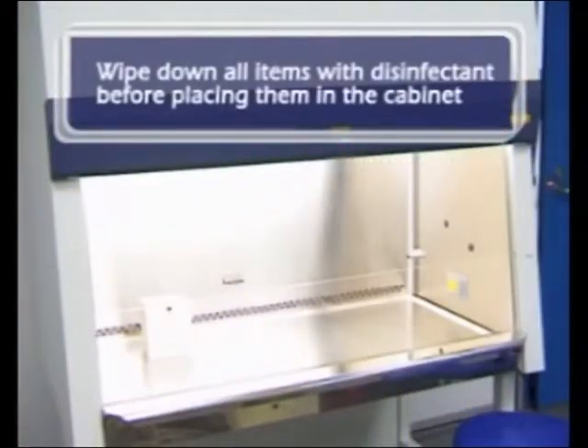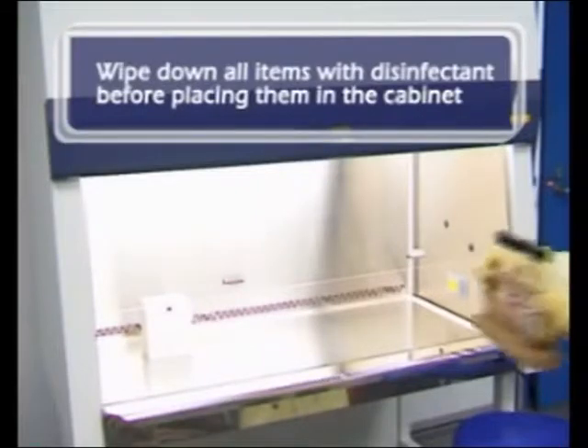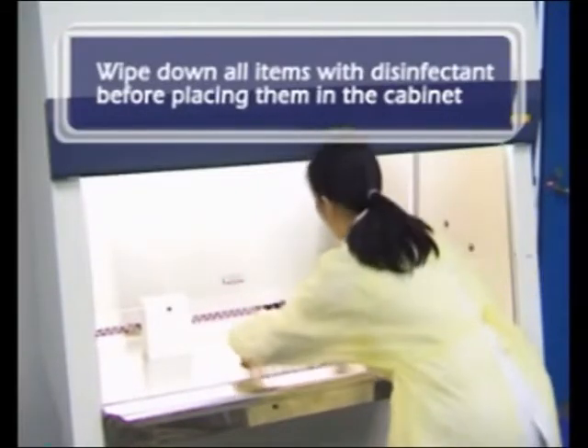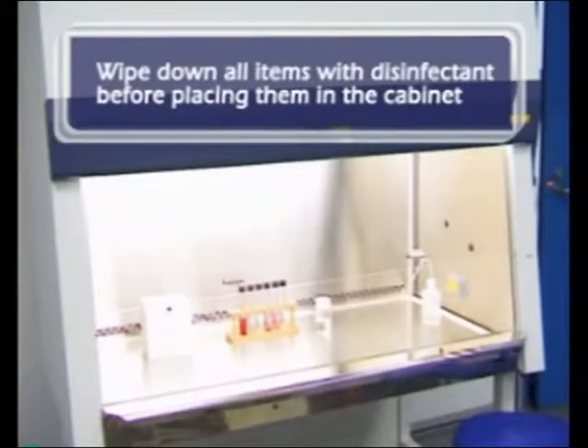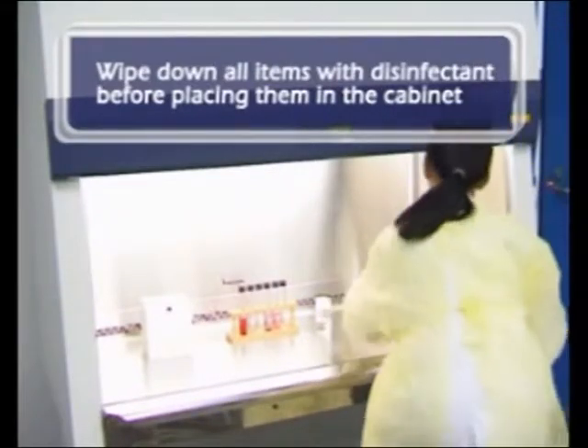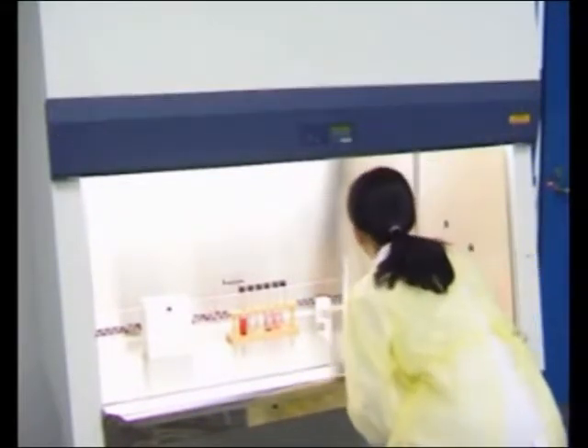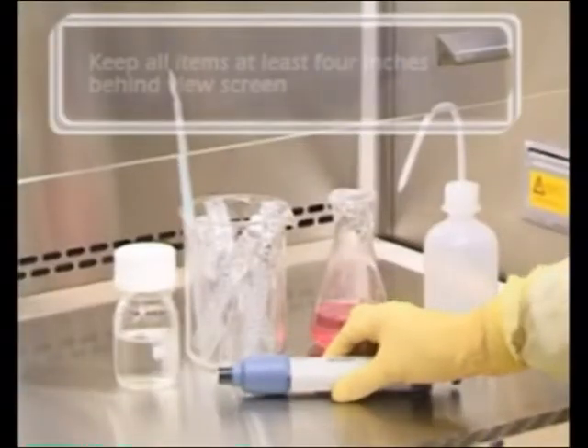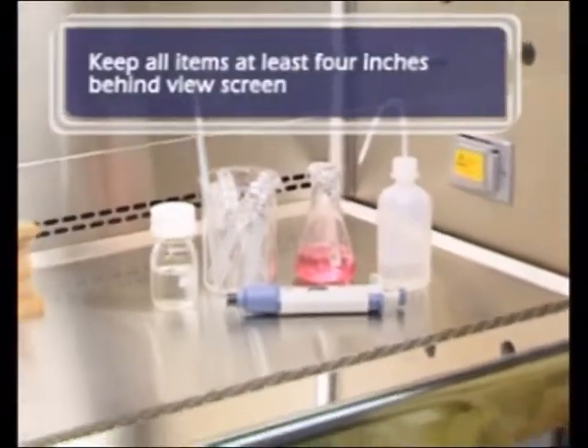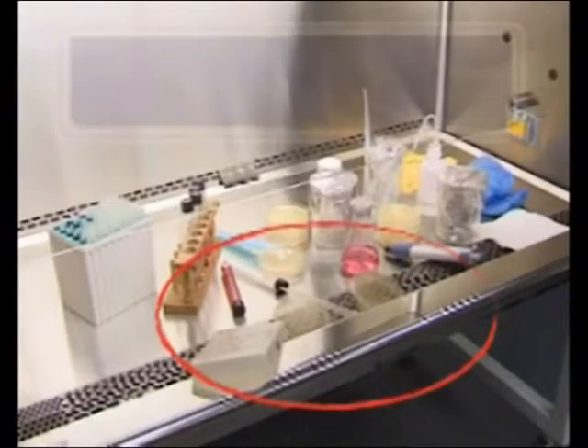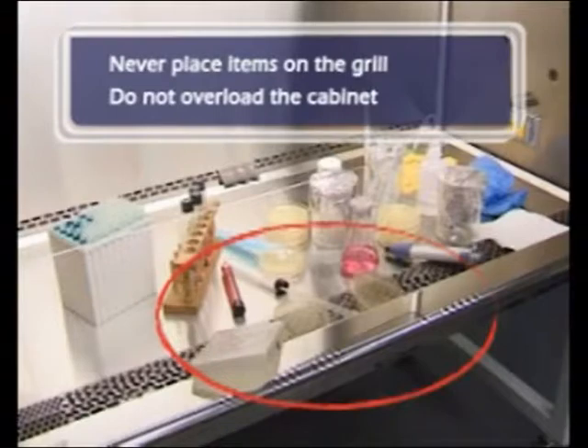Wipe down the external surface of items with disinfectant and load the cabinet work zone with all the items you will need for your work. Check the list you have made earlier on. Make sure you have everything you need before you start. Nothing should be taken out of or put in the biosafety cabinet once you begin working. Pay special attention to the front air grill, which must not be covered as illustrated here. Disruption to the inflow of air into the cabinet will compromise the cabinet performance. The cabinet work zone should not be overloaded.